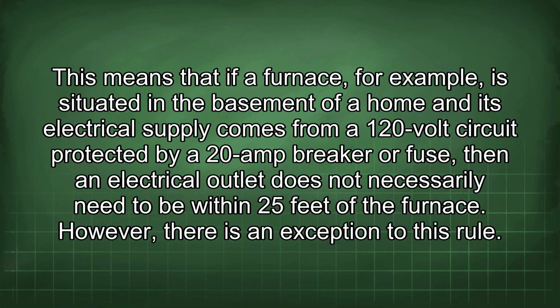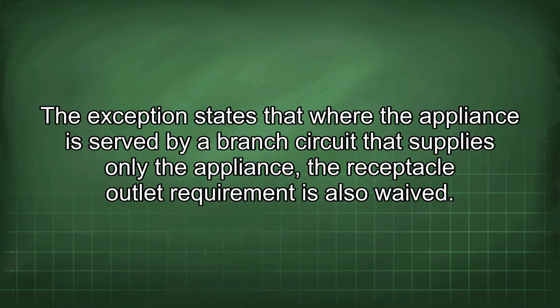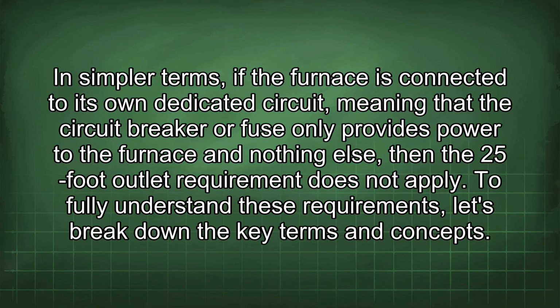However, there is an exception to this rule. The exception states that where the appliance is served by a branch circuit that supplies only the appliance, the receptacle outlet requirement is also waived. In simpler terms, if the furnace is connected to its own dedicated circuit, meaning that the circuit breaker or fuse only provides power to the furnace and nothing else, then the 25-foot outlet requirement does not apply.